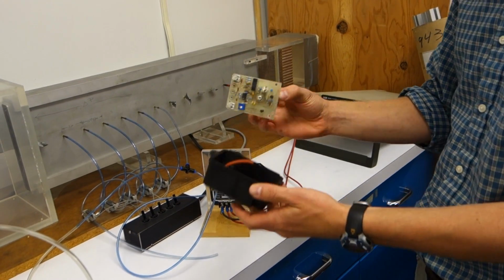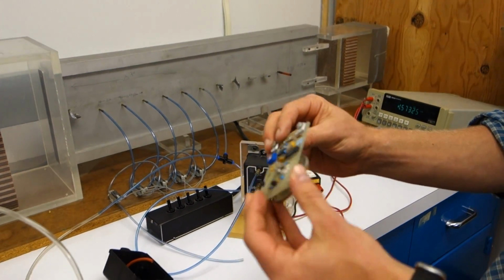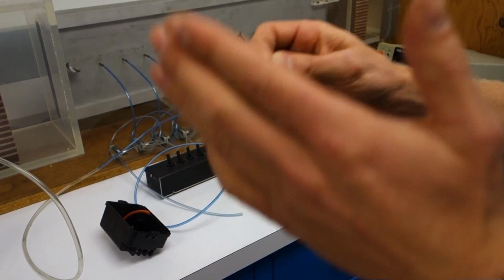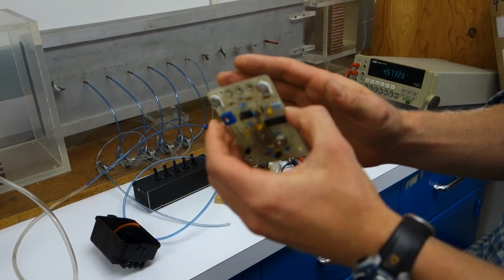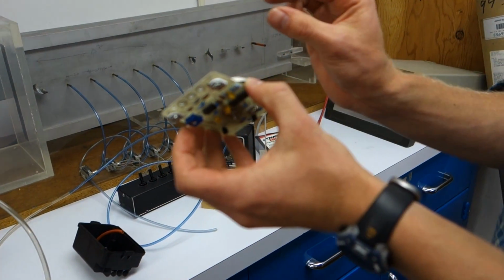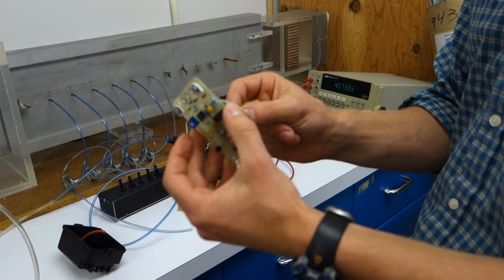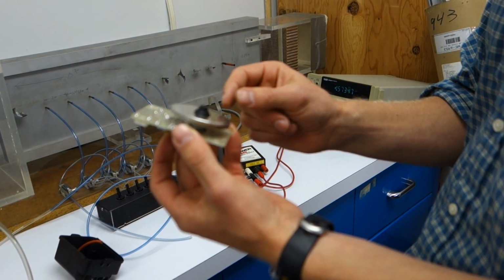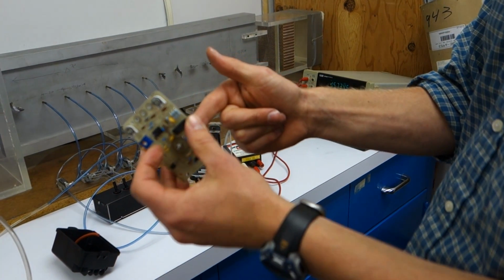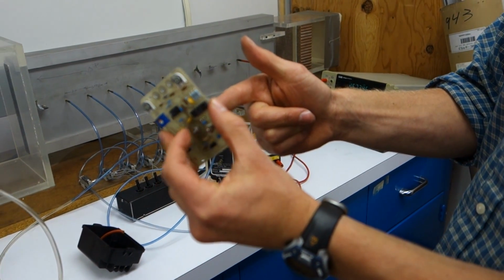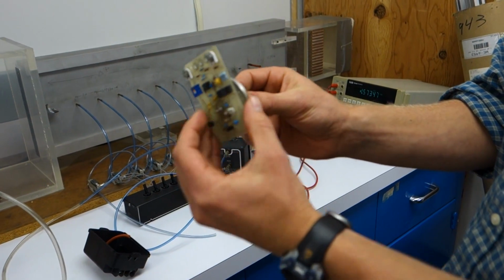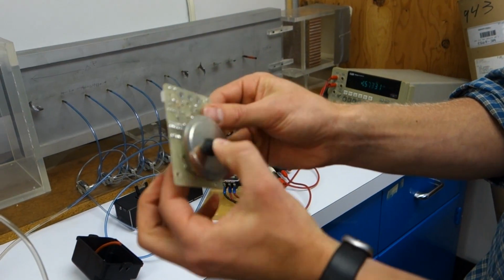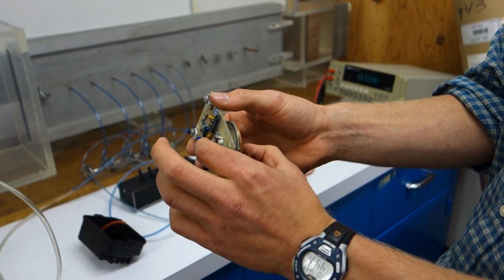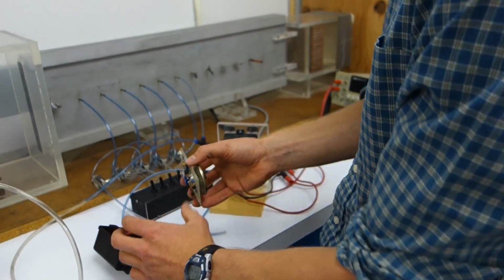So the interior looks like this. There's a capacitor with two parallel plates, right? And the capacitance is proportional to A over D, where A is the area of the plates and D is the separation between the plates. So if you change D, you can pick up different capacitance values in your circuit. And we change D by simply applying a net force that pushes the plates one way or the other. There's one port open here, another port over there, and it's as simple as applying a different pressure across them, which changes the separation.